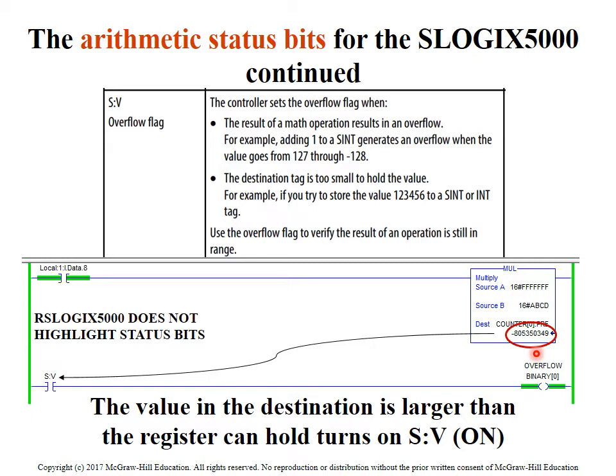So what it's doing is going past positive into the negative number, so it went over the top, right? That's why it's a negative number as well. So it's not an accurate number. You couldn't use this number as this multiplied by that equals this. It wouldn't come out properly because the number of bits available in that destination can't support the number that this times this would equal.